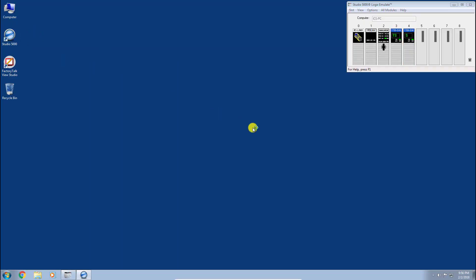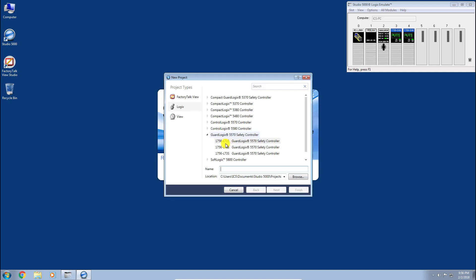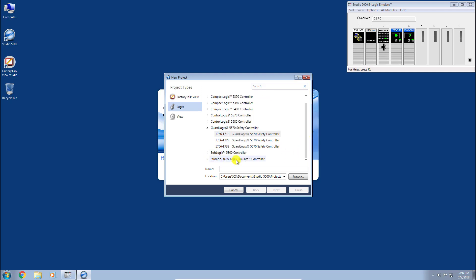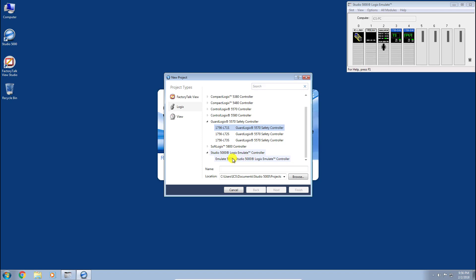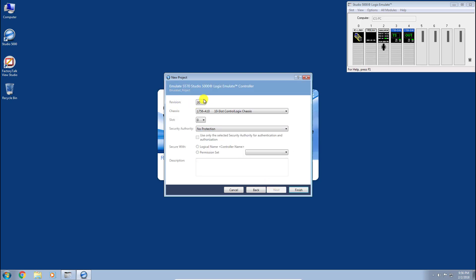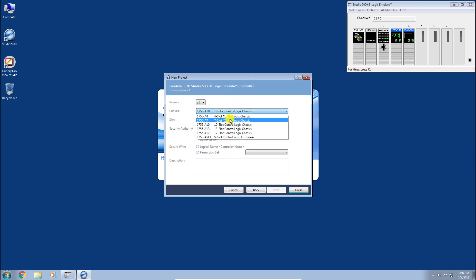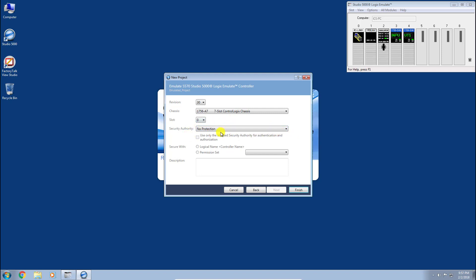Let's head over to Studio 5000 and launch it. We're going to create a new Logix project and scroll down until we see the Studio 5000 Logix Emulate controller. We'll click the arrow and select the Emulate 5570 controller. We'll name it 'Emulated Project,' click Next, use version 30, set it to a seven-slot chassis, no protection. Importantly, the emulated processor is in slot 2, not slot 0, so we change that and click Finish.